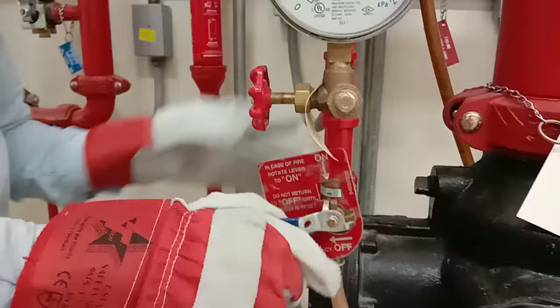I want to emphasize one more thing here. We have this ball valve, which should always be in the off position. If you want to open the system manually, just open this one. The moment you open this one, the water will discharge from this line, all the way to the drain valve, and the system is activated.